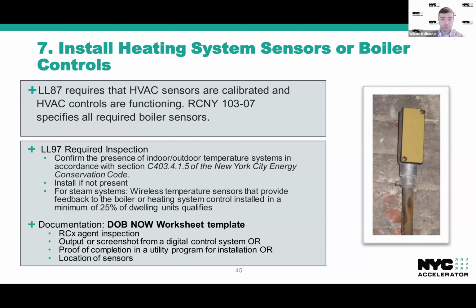This is another measure that has special reporting requirements under DOB now. So there's going to be a specific worksheet and template to be provided that the RCX agent needs to confirm inspection, and then documentation such as a screenshot or output from the digital control system, proof of completion in a utility program that incentivizes this work, or documentation of the location of sensors is also going to be required to comply with this measure.